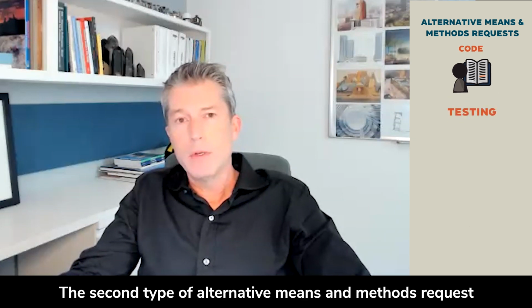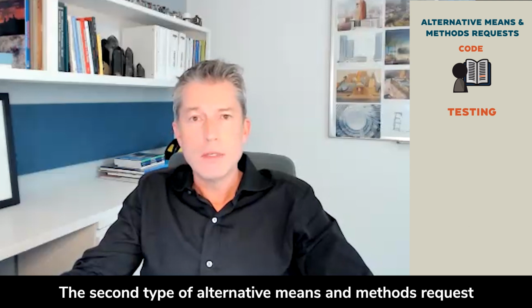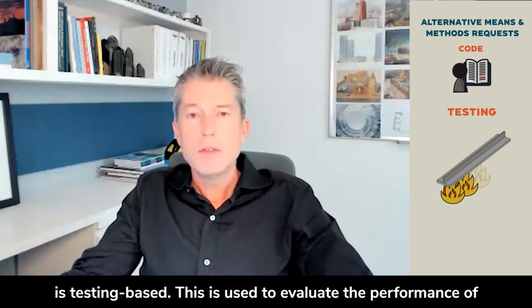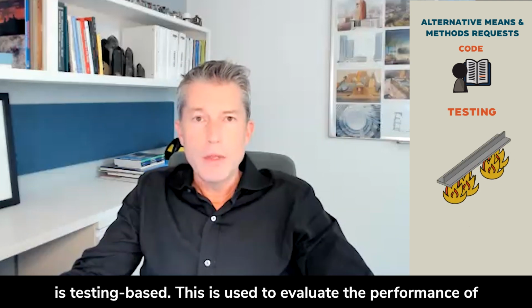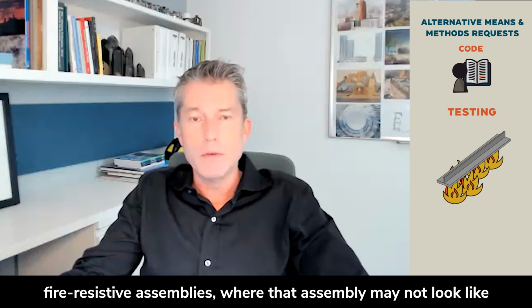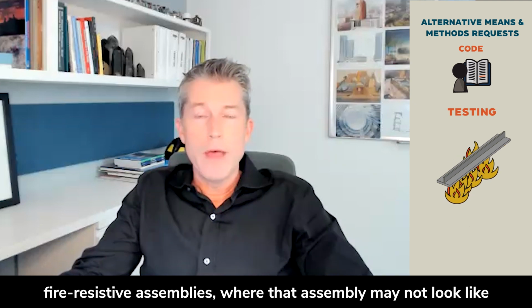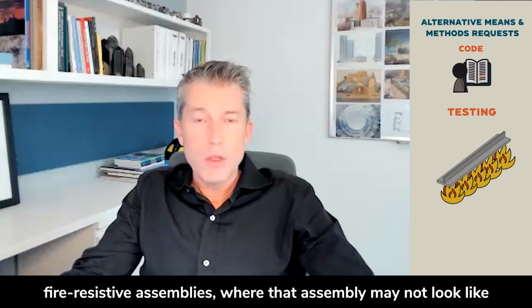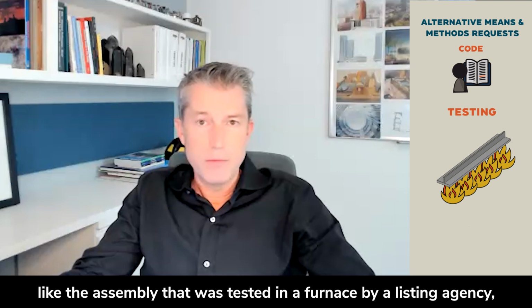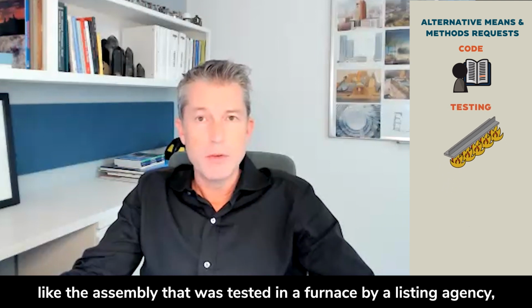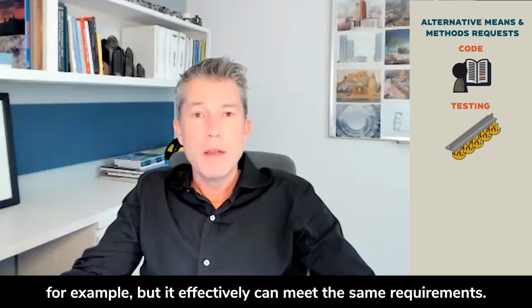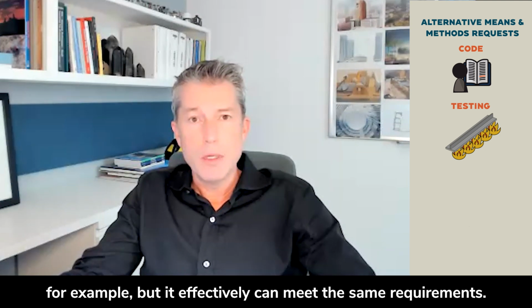The second type of alternative means and methods request is testing based. This is used to evaluate the performance of fire resistive assemblies, where that assembly may not look like the assembly that was tested in a furnace by a listing agency, for example, but it effectively can meet the same requirements.